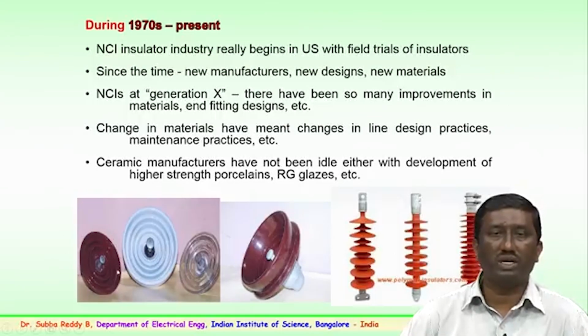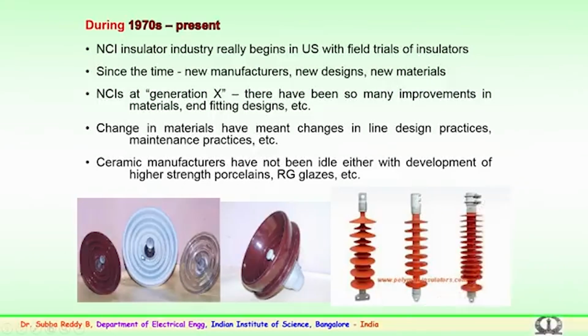So, these are the various disc insulators which have been shown here. These are the ceramic insulators. This is again a ceramic insulator, which is used with a higher creepage length for a particular area. Then this is the glass type of insulator, and this is the anti-fog insulator, particularly for areas where the transmission lines are passing through high fog density locations.